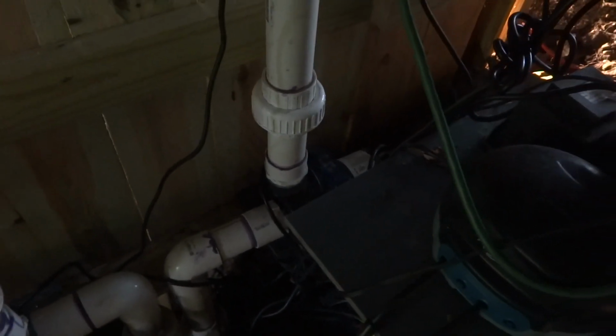On the other side here is our big 8,000 gallon per hour pump, and again we have the different unions so we can take it out even if we have to fix it. It goes in 2 inch, comes out 2 inch. On the T we go and break it down to 1.5 inches.